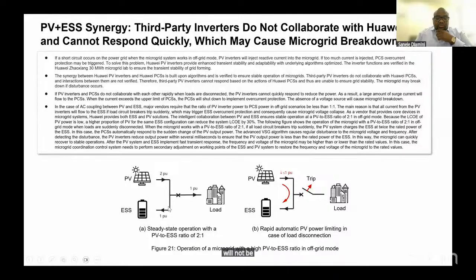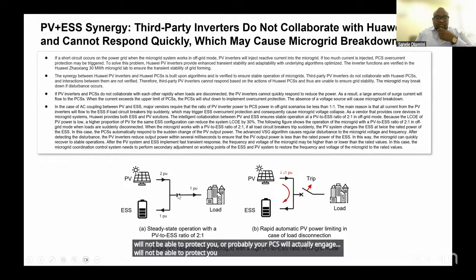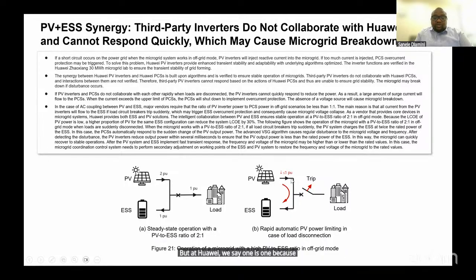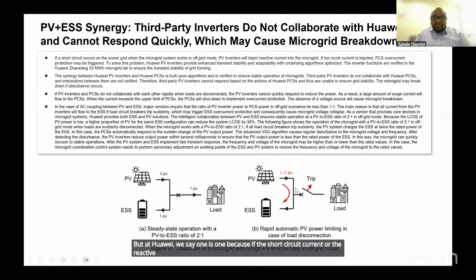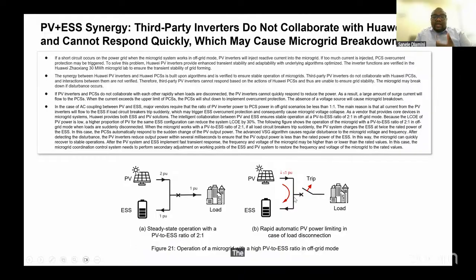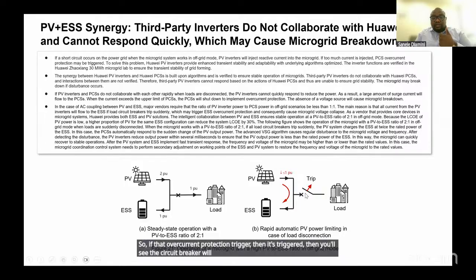will not be able to protect you, because it will leave this thing open. And when it's open, that means all the short circuit will go to your load and then probably cause problems in your load. But at Huawei, we say 1:1 because if the short circuit current or the reactive current is happening on the PV side, the PCS will then engage the overcurrent protection trigger. If the overcurrent protection is triggered, then you'll see the circuit breaker will open, or the isolator will open to protect the load on the side. So this is what Huawei supports on our side.